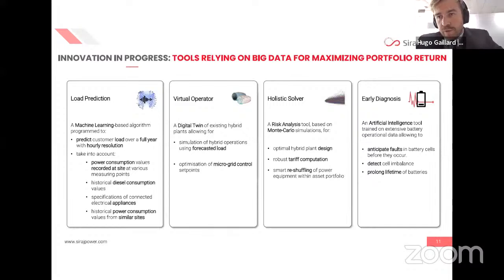Now, we also need to be able to set what we call the operating philosophy. So the operating philosophy is how we operate the microgrid at an intraday scale. So basically, we have an energy management system at site, which will take the decisions on whether to charge the battery, when to discharge the battery, when to switch on and off generators, and which one. And in order to take those decisions, we need to define some operating set points. And the whole idea is to have a digital twin of our hybrid power plant that will be able to simulate the behavior over the next 24 or 48 hours, to be able to change those set points if necessary based on the load prediction. So this is a second module that we're currently developing.